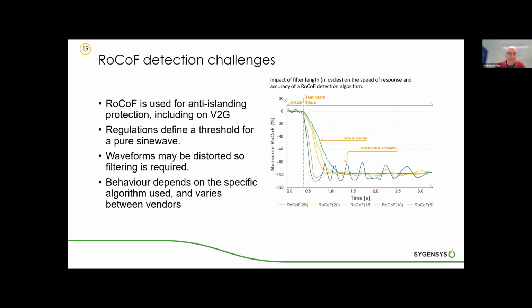Now we know that regulations define a threshold for RoCoF tripping based on a pure sine wave, but we do know also that waveforms may be distorted, so filtering is required within the relays. And the behavior of the relay therefore depends on the specific algorithm being used by the vendor, and these do vary between vendors. So the chart on the right comes from a project that Peter and I did at Brunel University a little while ago, and it shows the behavior of one vendor's relay with different levels of filtering. And you can see that the response of the relay will depend on the level of filtering that's applied. And this will also vary between different vendors.